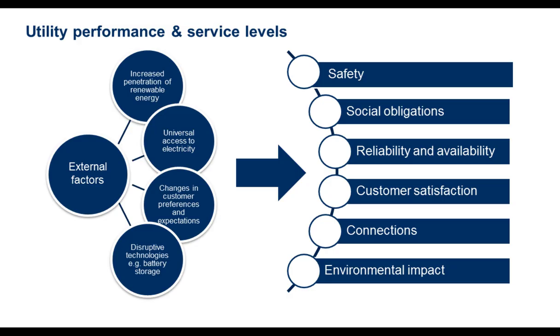Key indices are used to compare the performance of utilities. Outside Europe, SAIFI - System Average Interruption Frequency Index - and SAIDI - System Average Interruption Duration Index - are used. Here in Europe, we use a slightly different convention: instead of SAIDI we refer to CML, Customer Minutes Lost, and instead of SAIFI, Customer Interruptions.